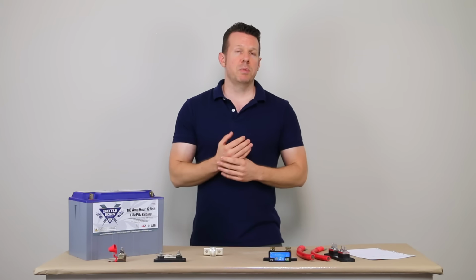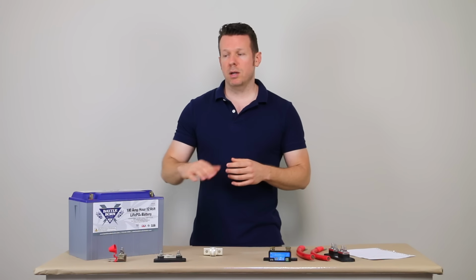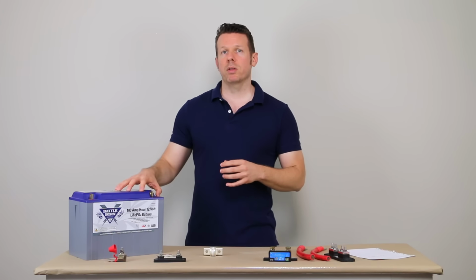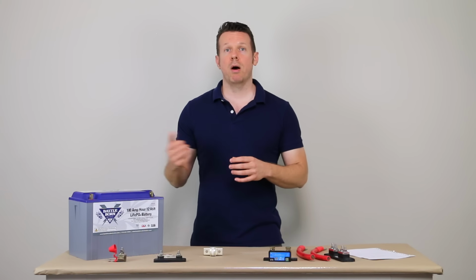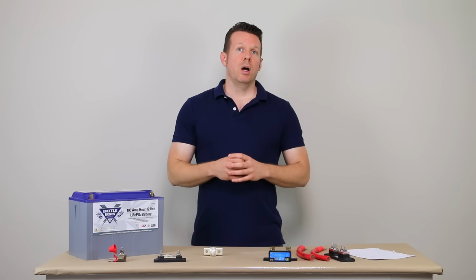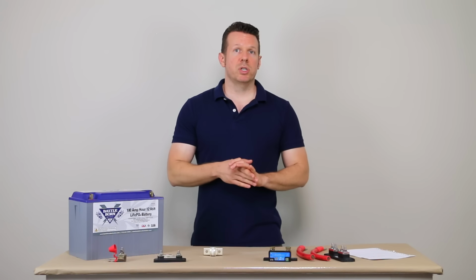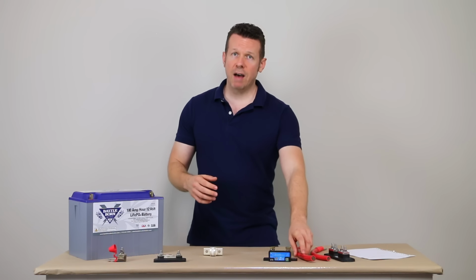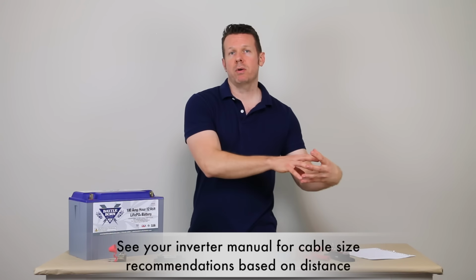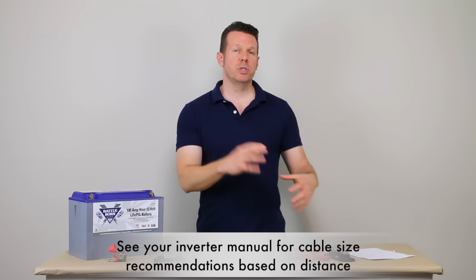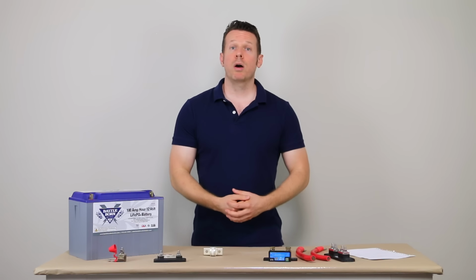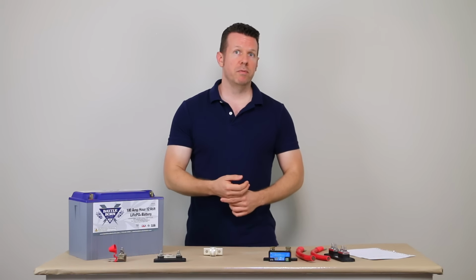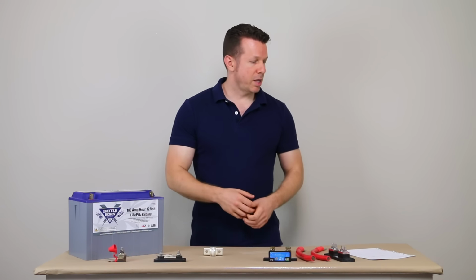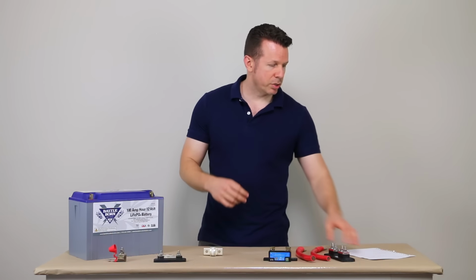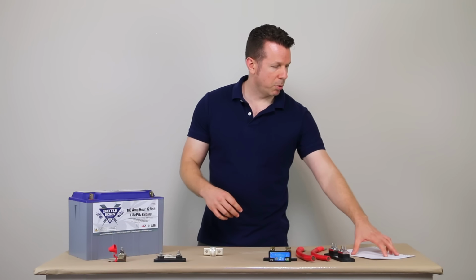So that's something to look out for. DC ripple can microcycle your batteries and wear them out faster, and it can also wear out your inverter. You just want to eliminate that from your system. So having cables from your battery bank to the rest of your system that are too skinny can cause DC ripple and shorten the life of your components. So that's mistake number 2, having lines that are too small that cause DC ripple.